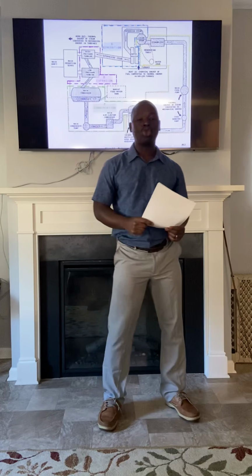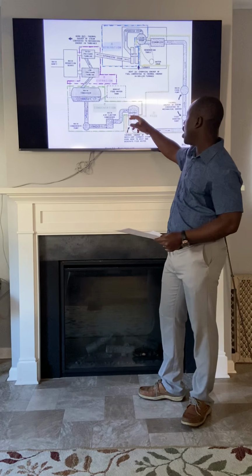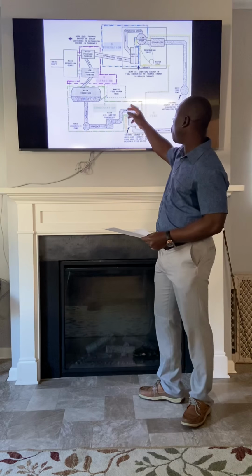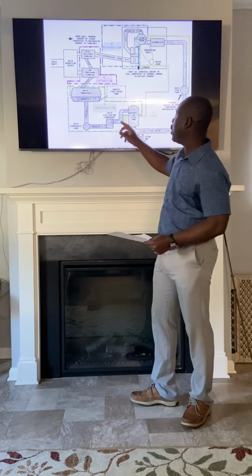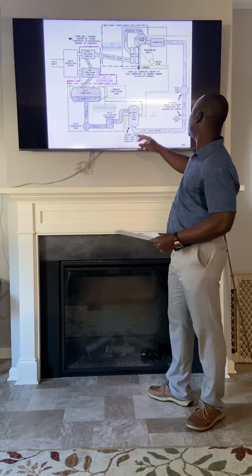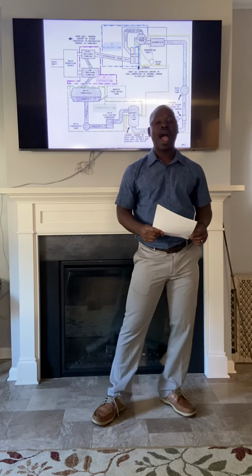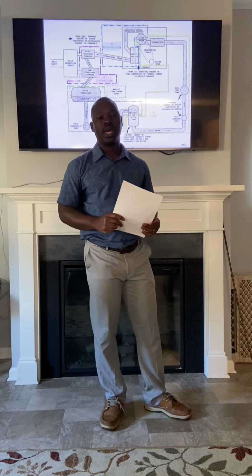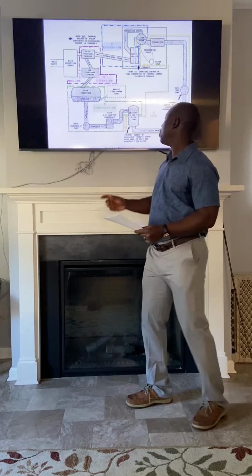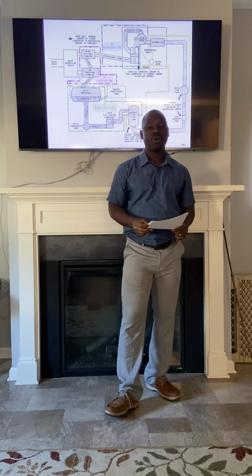My sources indicate that the deaerated feed tank is divided into two portions. We have the upper half and the lower half. The upper half marks the end of the condensation phase, while the lower half initiates the feed phase. The deaerated feed tank has three main purposes. It deaerates feed water, which means removes oxygen from the feed water. It preheats feed water and stores feed water.